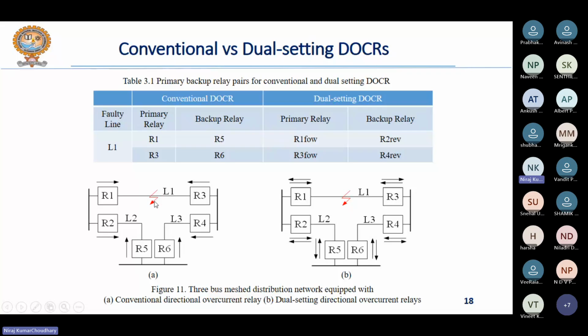So for the fault at line L1, in R5 you have the current flowing in the same direction as it is flowing through the relay R1. That's why R5 will be the backup for relay R1. Now, if for the same fault location relay R3 is considered as the primary relay, then using the same principle and concept, you can see that R6 will be the backup relay for relay R3. Similarly, for different fault locations on lines L2 and L3, you can formulate the primary and backup relay pairs.